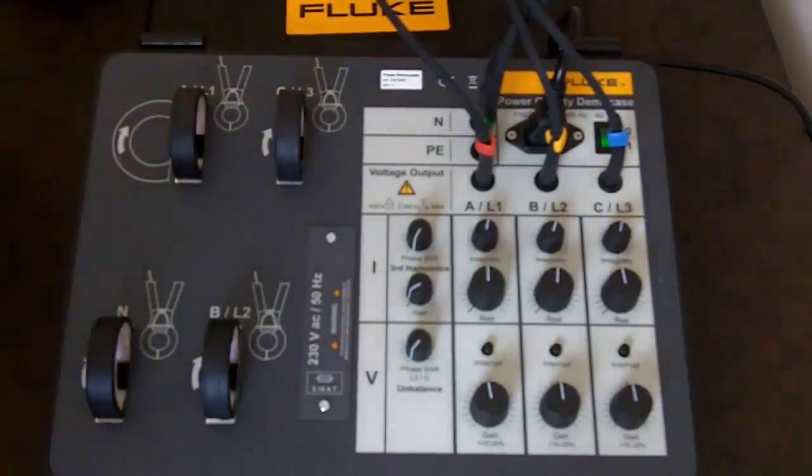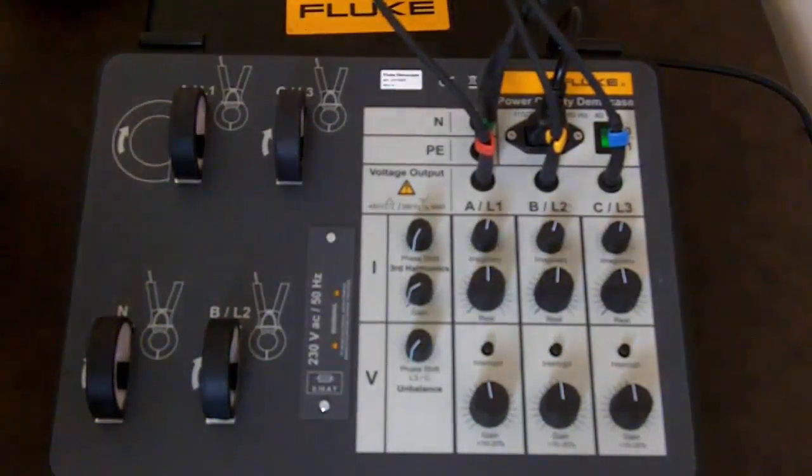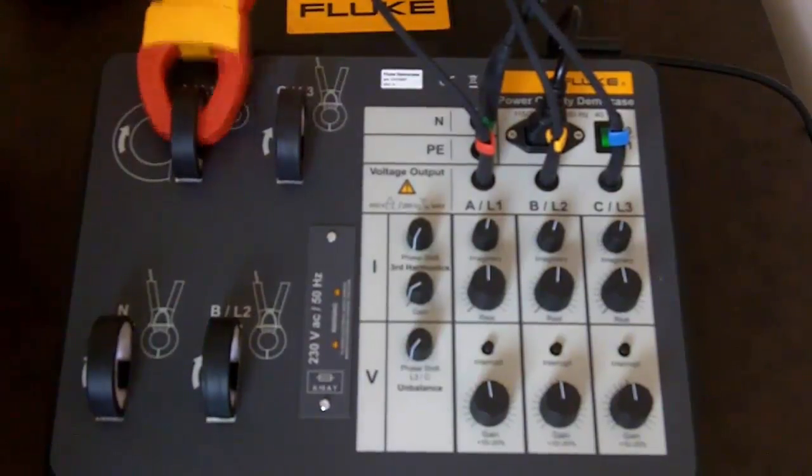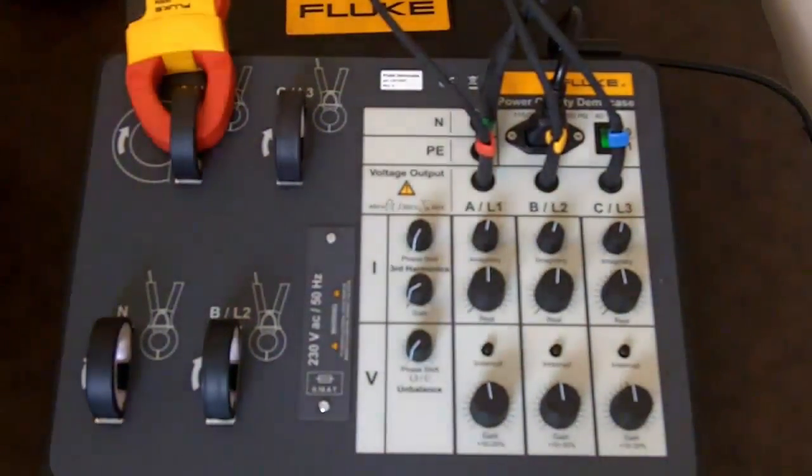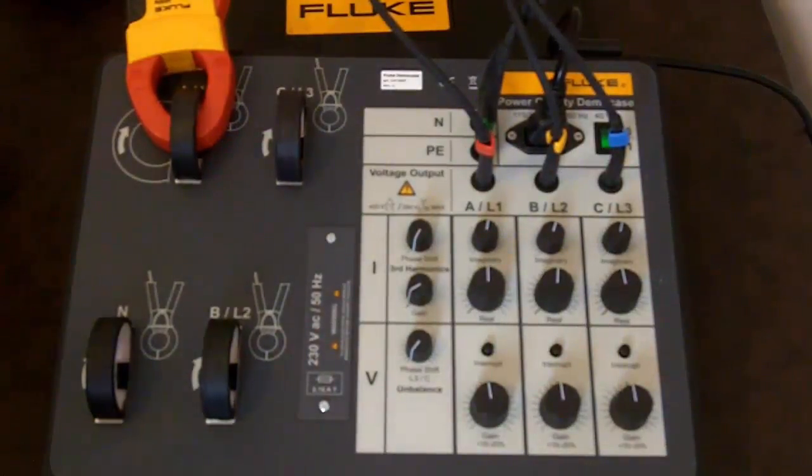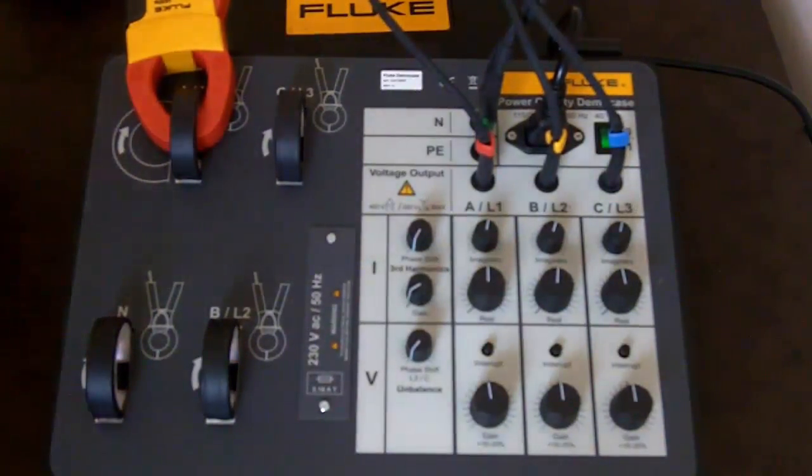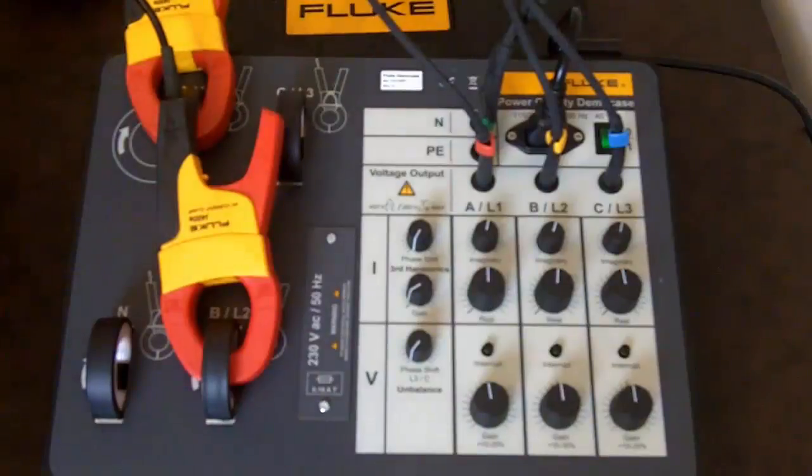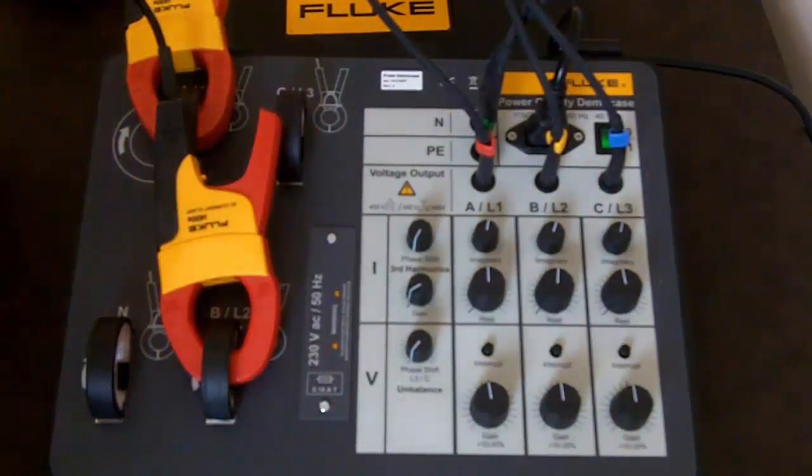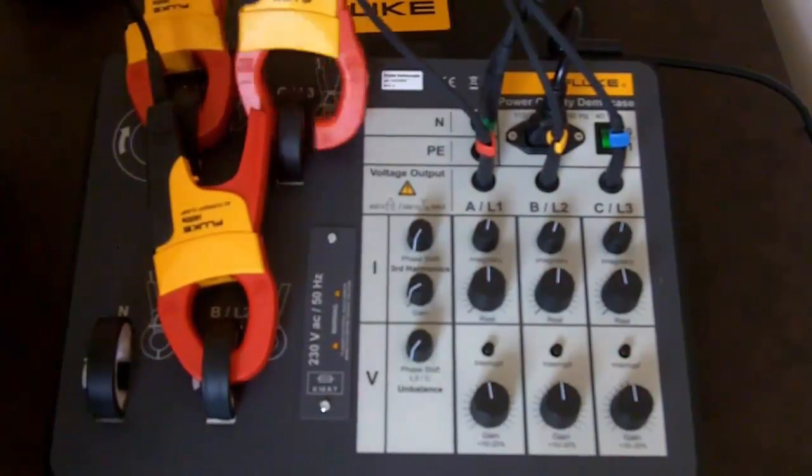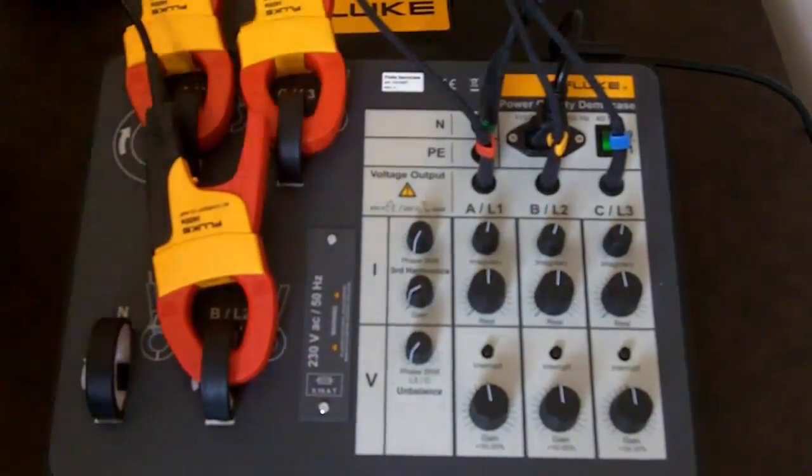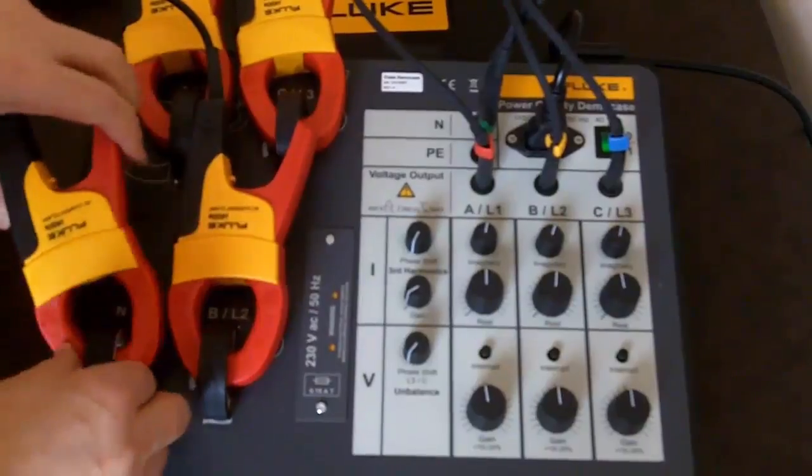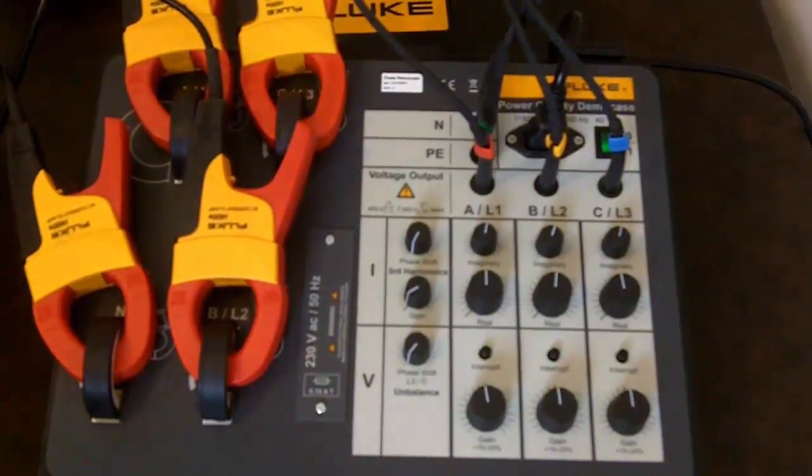We can now connect up for current. We will use current clamps in this case observing the polarity which is indicated on the case. So first of all we will go to phase A, making sure that that is snap shut. Then phase B or 2. Again make sure that is tight and shut. Next is phase 3 or C. Once again click to make sure we measure the right current. And then lastly we will connect to the neutral. Push it inside the ring. And now we are ready to make a measurement.